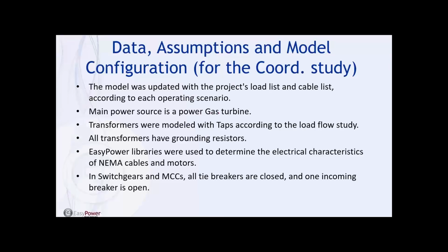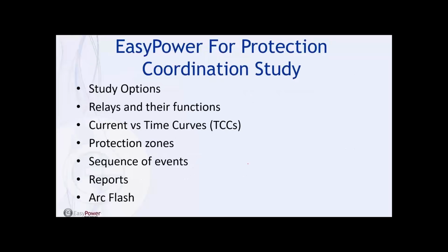The main power source is the gas turbine. The transformers were modeled with taps according to the load flow - in our load flow, one of the results was the taps for each power transformer. We are using all the libraries in EasyPower, including the information from relays as well. And as before, all tie breakers are closed, so one incoming breaker is open.